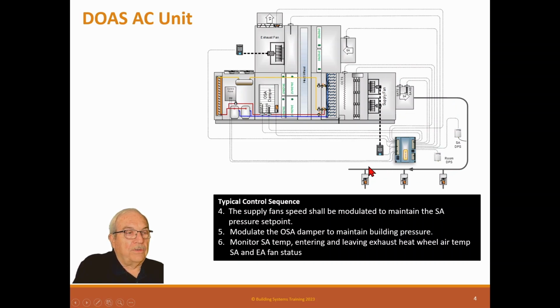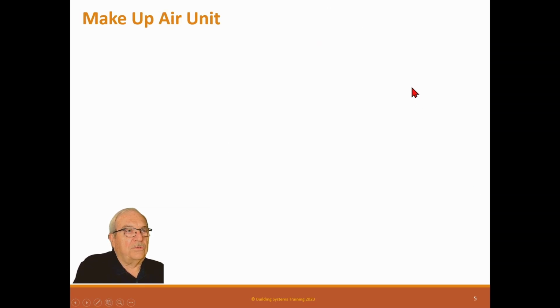And remember, this is not trying to do economization. We don't have a big enough system. This system is just big enough for the outside air requirements, not full economizers of these air handling units. That would not be good to try to do. We have humidity in here because we're trying to dehumidify. So we're going to dehumidify off room conditions. We have status conditions to see what's going on.